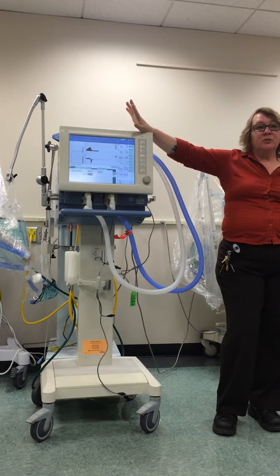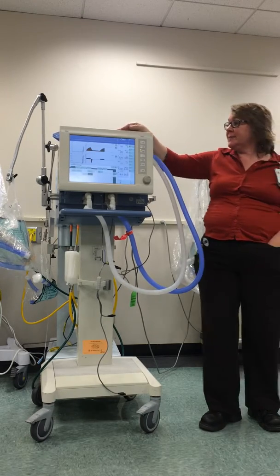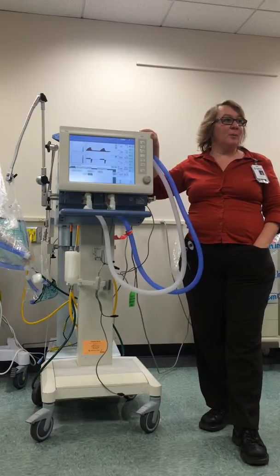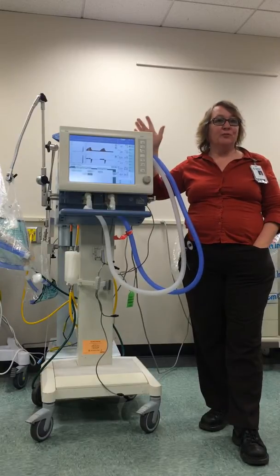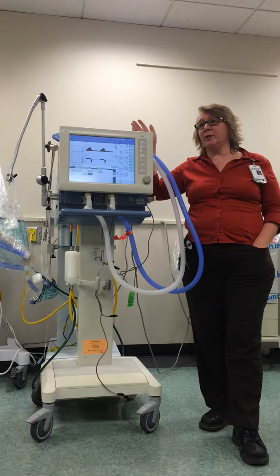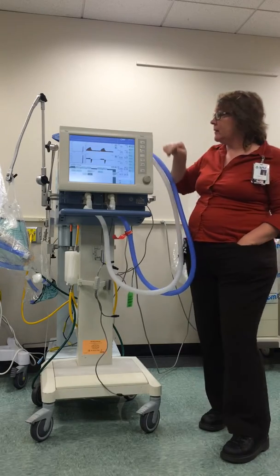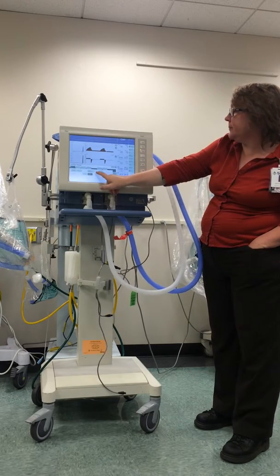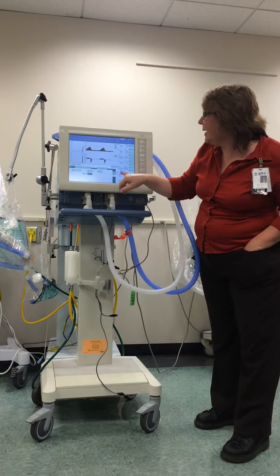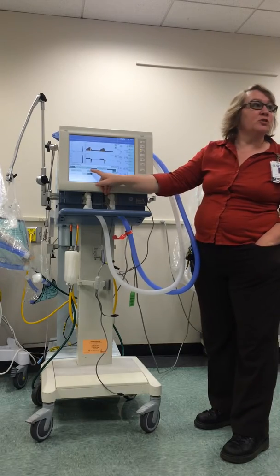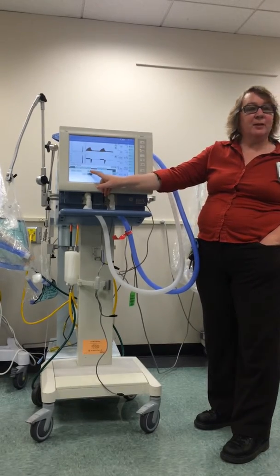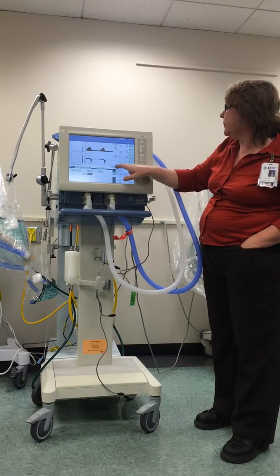See, that's what you can see up here. And you'll see in the beginning, I'm going to tell you to be in ACVC, and you're going to forget about the auto flow, and I'm going to come over and tell you you're not in ACVC because the auto flow's on. As long as auto flow's on, you're in PRVC. Right here, this one. Hitting that additional settings is also where you can get to your trigger. Remember your sensitivity, patient or flow. So that's where those are.